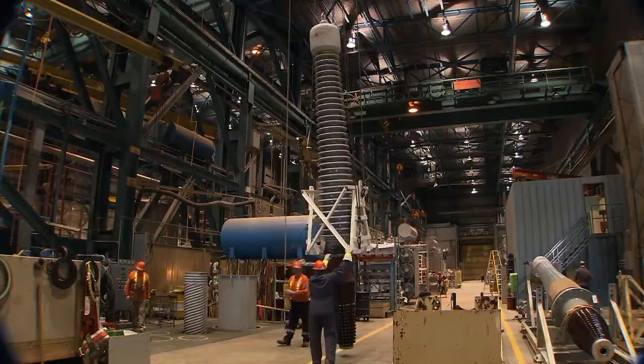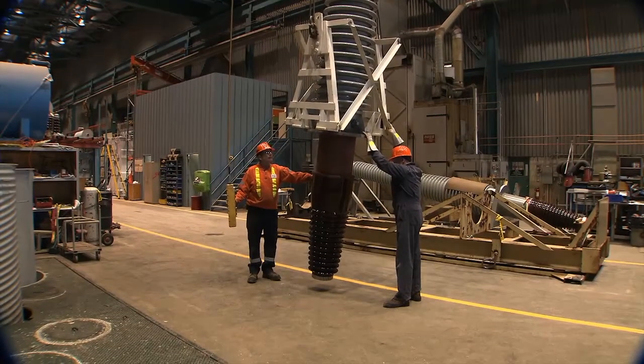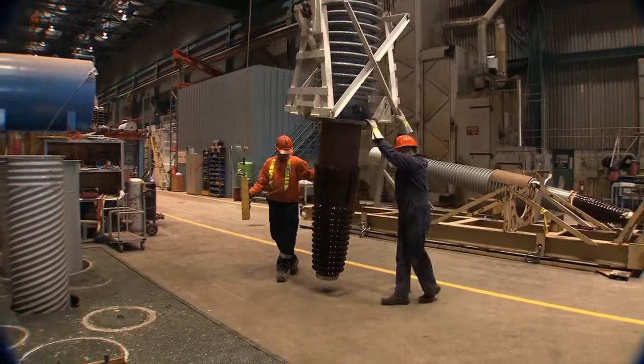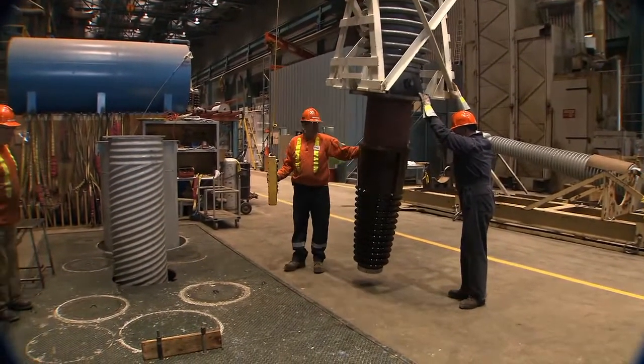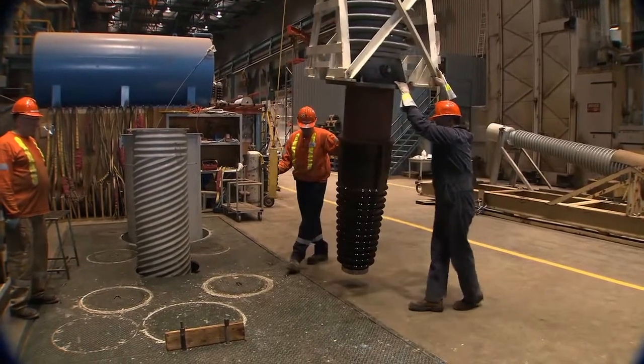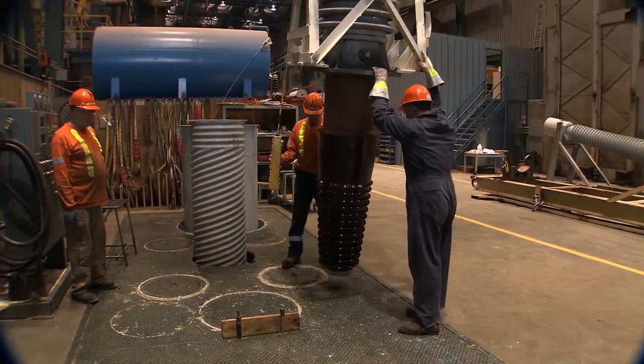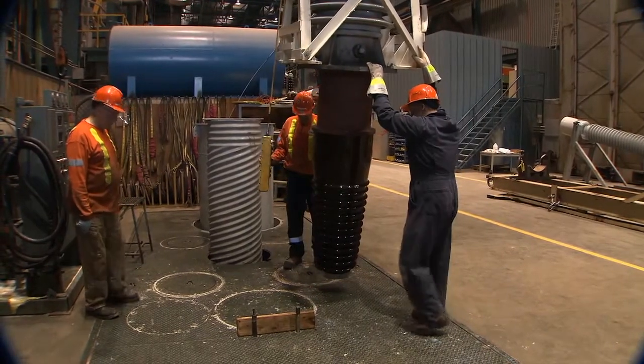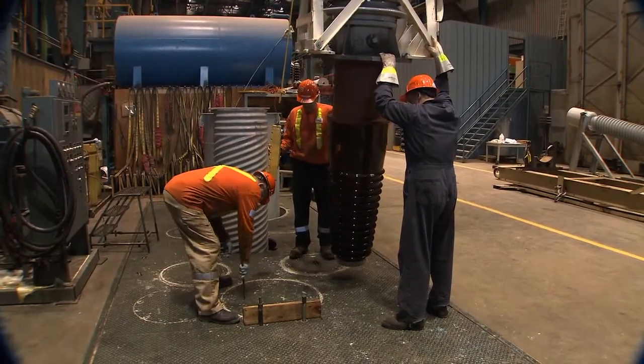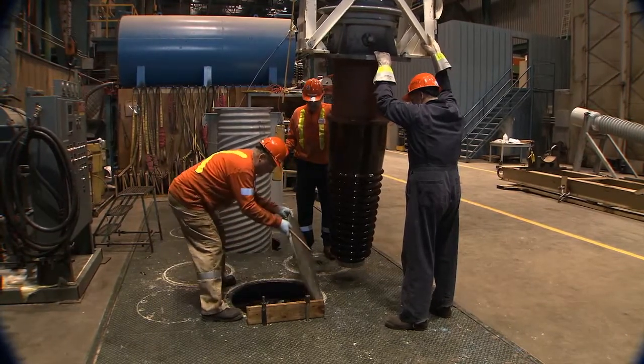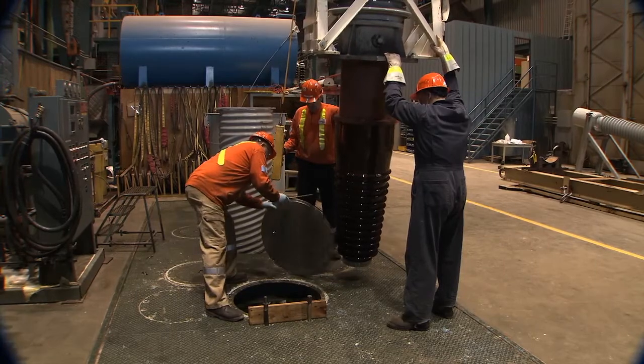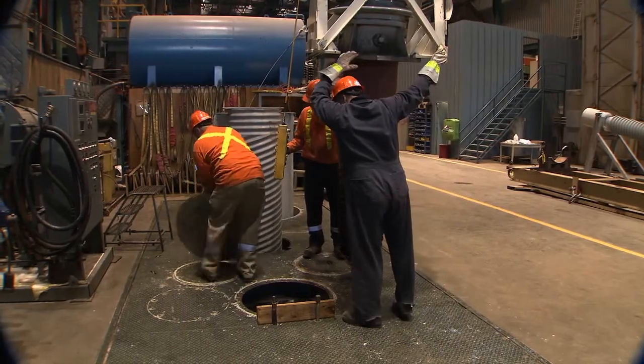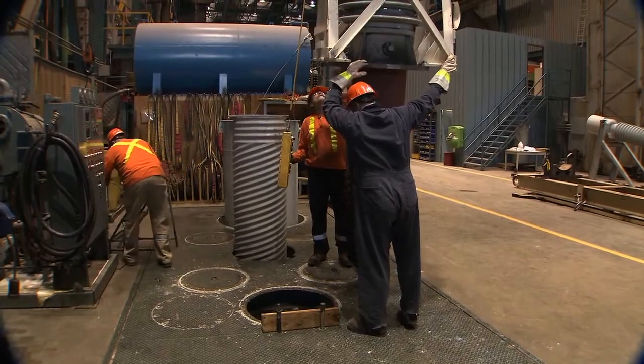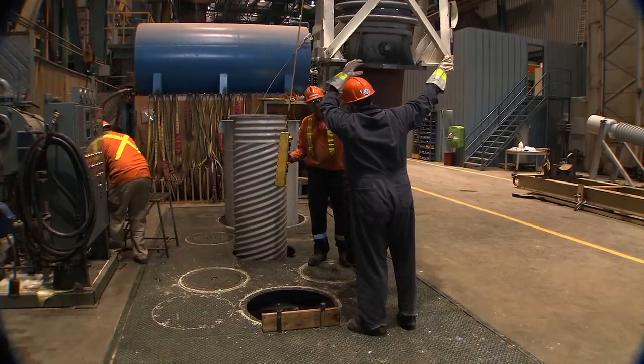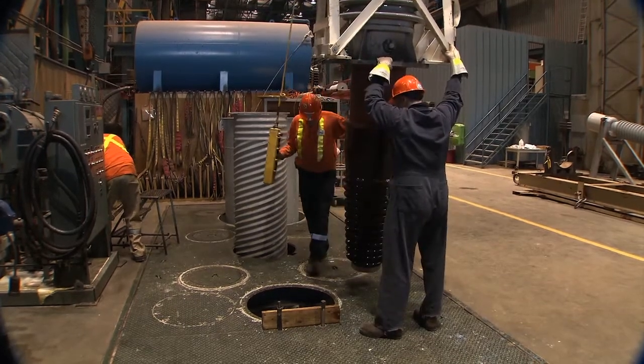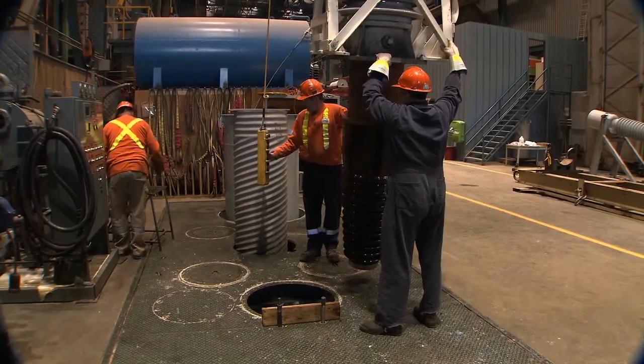Okay, coming east. I'm going to start taking it east. Move the bushing eastward towards the service well with guidance from a team member supporting to prevent it from swaying while it's being moved. Okay, Graham, you can go ahead and open up that hole. Remove the cover on the service well and roll it out of the way to a safe spot for storage. Center the bushing as much as possible as it is suspended above the well. Yep. Okay, Graham? Yep.